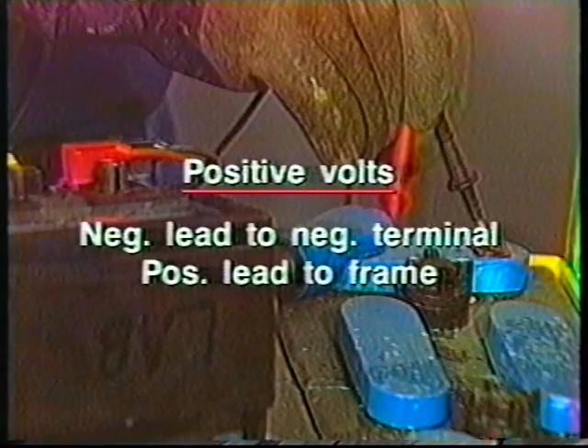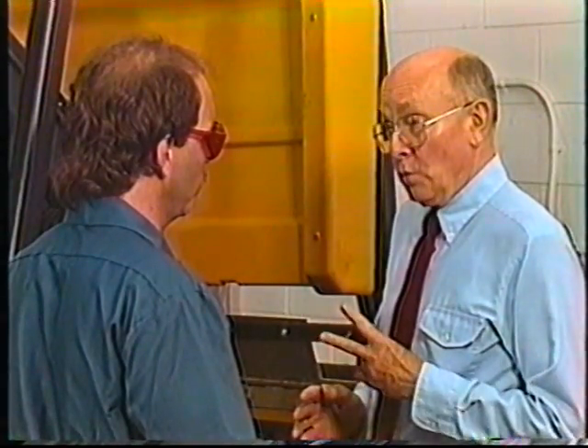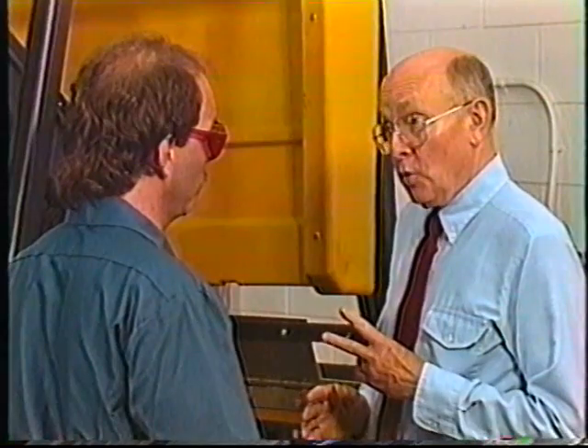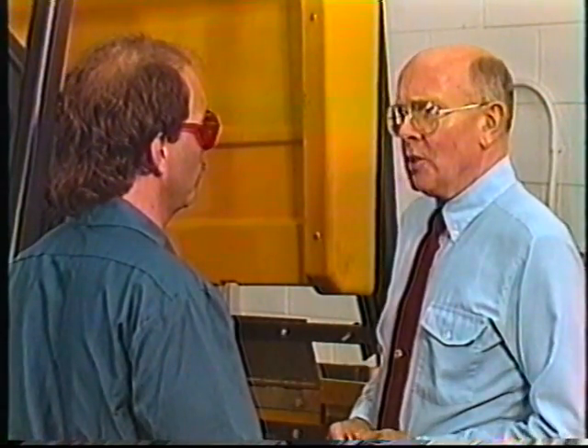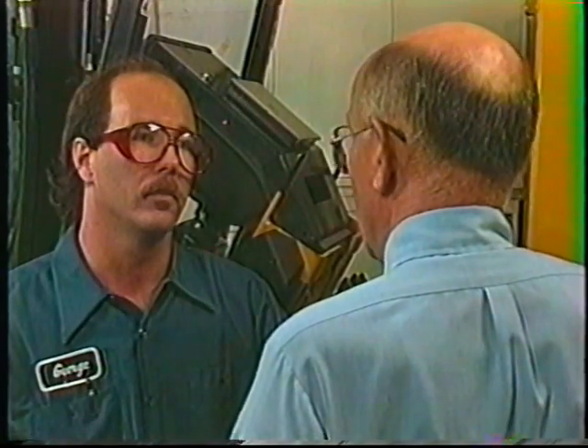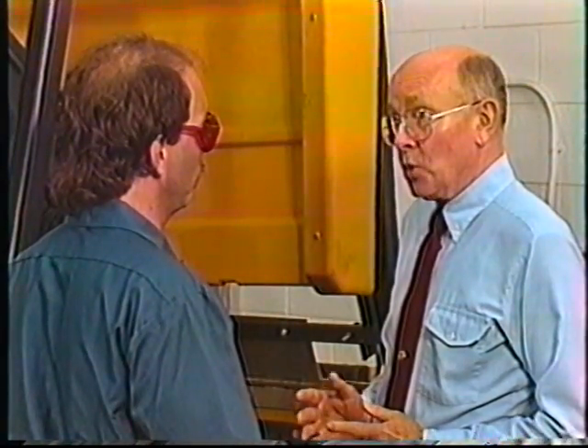Okay, the voltage reading on this 36-volt battery is 24 volts. We call that positive volts because the negative meter lead is on the negative battery terminal and the positive lead is on the frame. Divide the voltage reading you get by 2 because each cell is worth 2 volts. That gives you a good indication of which cell of the battery is leaking. Our reading was 24 volts. When we divide that by 2, we get 12.